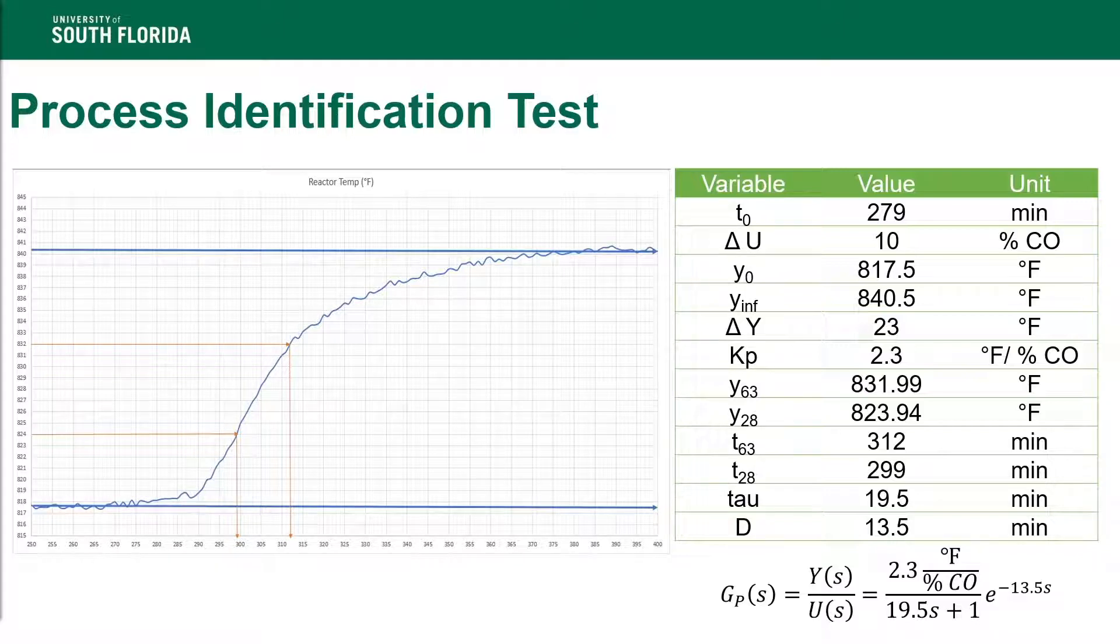From there, we cut the sample down to the window where the ambient temperature fluctuated the least. This was from the time 250 to 400. During this period, we were able to determine the gain of the system, the time constant tau, and the delay using the 63% and 28% response method.